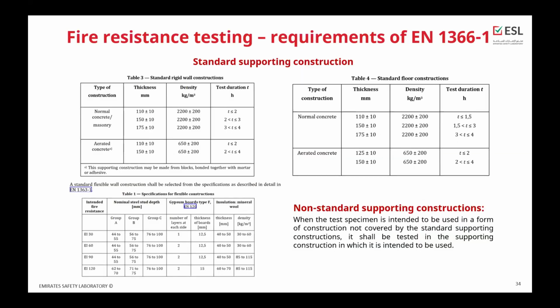What is unique in this standard is that EN 1366-1 and parts 8 and 9 define standard supporting construction and non-standard supporting construction. Standard supporting construction is defined in these three tables, and it gives you some opportunities. For example, if you choose to test your duct passing through the flexible supporting construction, you will get in the field of application the possibility to install your duct on site within the drywall system, AAC blocks or concrete.